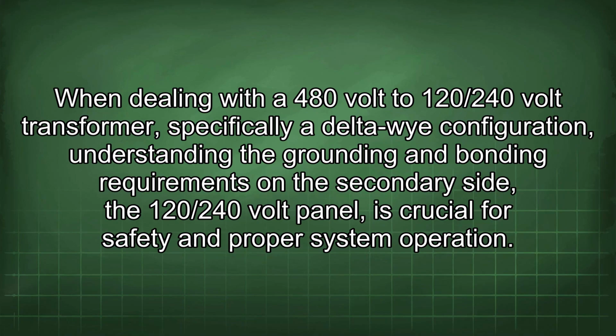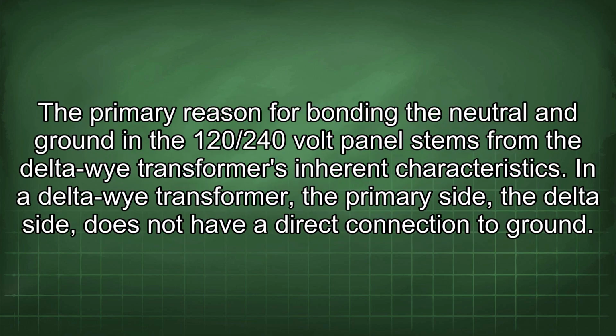When dealing with a 480 volt to 120/240 volt transformer, specifically a delta-wye configuration, understanding the grounding and bonding requirements on the secondary side, the 120/240 volt panel, is crucial for safety and proper system operation. The primary reason for bonding the neutral and ground in a 120/240 volt panel stems from the delta-wye transformer's inherent characteristics.